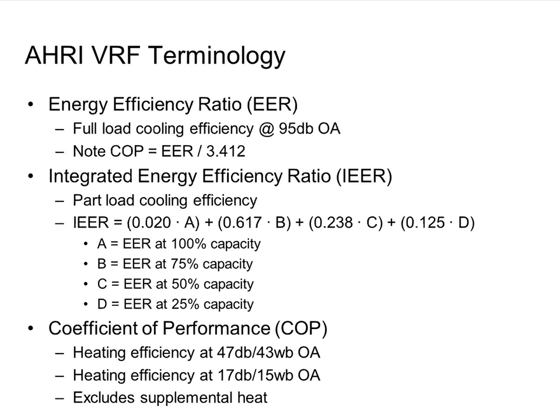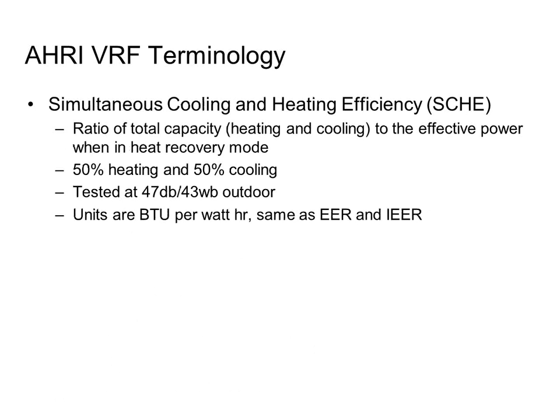So we got those 4 ratings: EER, IEER, COP, and COP 17. Then we have a 5th rating for VRF, because there wasn't enough rating systems, right? So unlike all the other products, there's 5 different ways these things are getting rated. It's the simultaneous cooling and heating efficiency. And because we're the HVAC industry, we've got to make that into a 4-letter acronym, so it's SCHE. You may have seen that on stuff or on an engineer's spec or a schedule for VRF systems and not even known what the heck that meant. So I'm going to try to explain what that basically means when you see it in the rating system here.